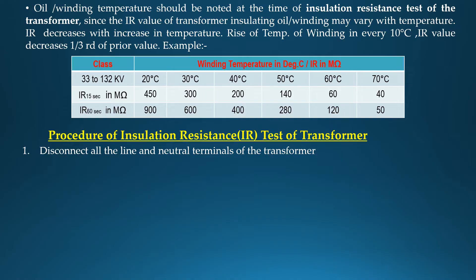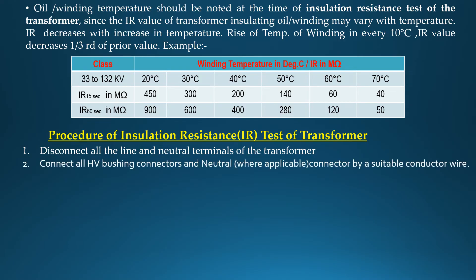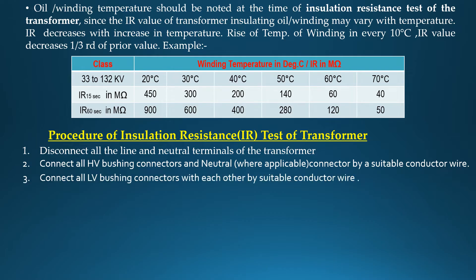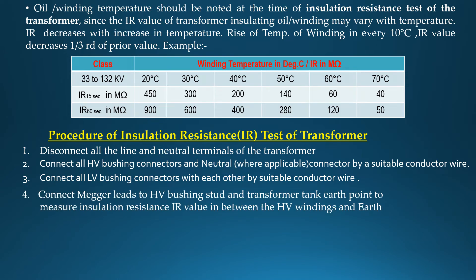Procedure of Insulation Resistance Test of Transformers. Step 1: Disconnect all line and neutral terminals of the transformer. Connect all HV bushing connectors and neutral connector by suitable conductor wire. Connect all LV bushing connectors with each other by suitable conductor wire. Connect megger leads to HV bushing connector wire and to the HV bushing stud and transformer tank earth point to measure insulation resistance IR value between the HV winding and earth.